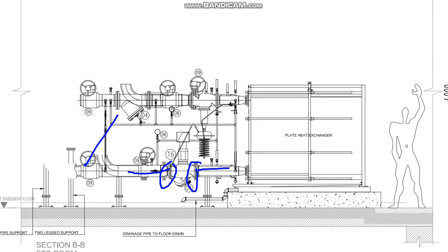So when it comes to flange sizing, we will see what difficulties we face when we order the material. Normally in the chilled water system we use three different types. First, the welding neck type of flange, where, as you see here, there is some projection. The pipeline coming from outside will be joined with this line, so you can weld it, and here you can see the bolts they have given. This is the flange connection area, and on one side the pipeline we can join with welding.